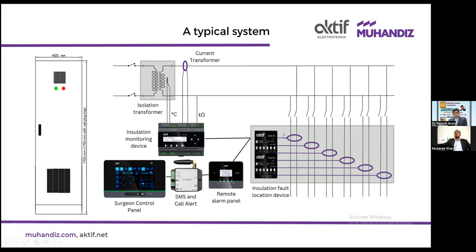Okay. All this information will be communicated to a remote monitoring panel through an RS-485 network, and that remote monitoring panel will display the data of all operation theaters together at one place. If there is an alarm, it will show that there is an alarm. Then, additionally and optionally, we can have an SMS and call alert system if there is a failure in the insulation fault or the isolation fault. Then we can have a surgeon control panel to monitor and control the complete equipment of the operation theaters together from a single place. This is a typical isolation panel, which is around 1.7 meter height and 405 mm width and depth.